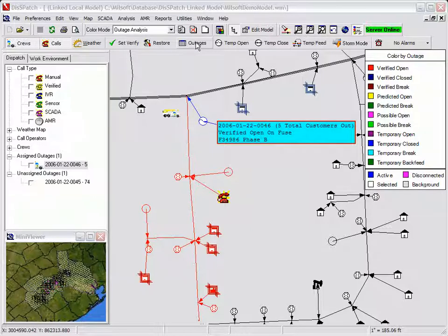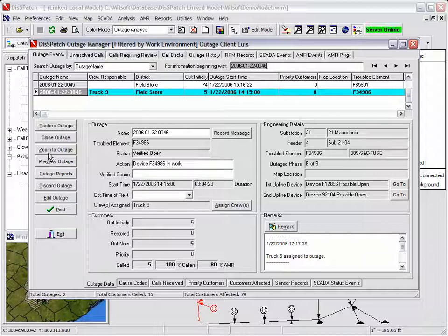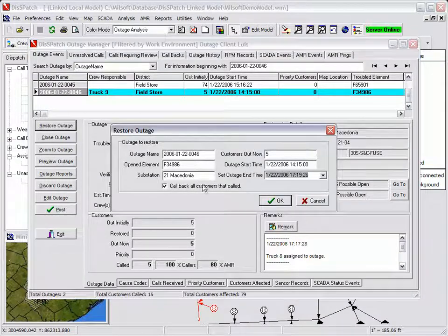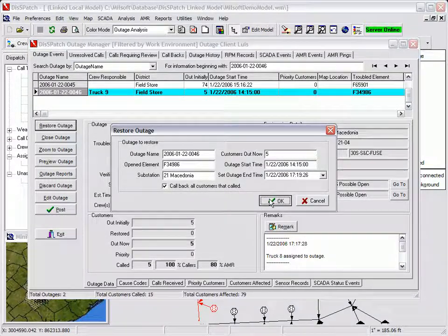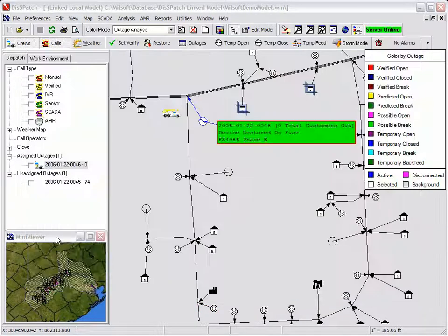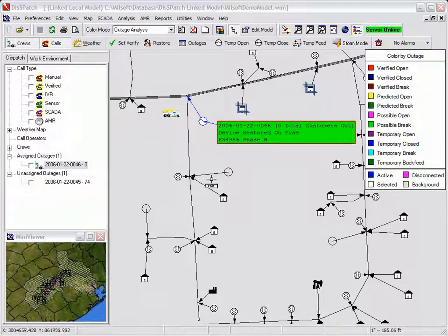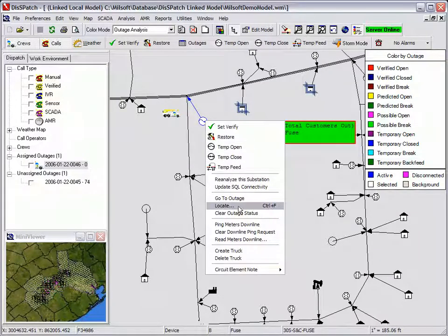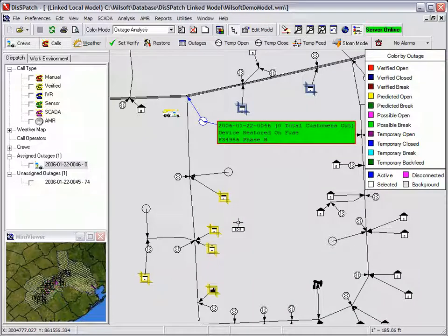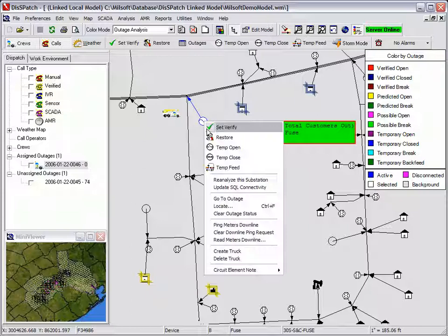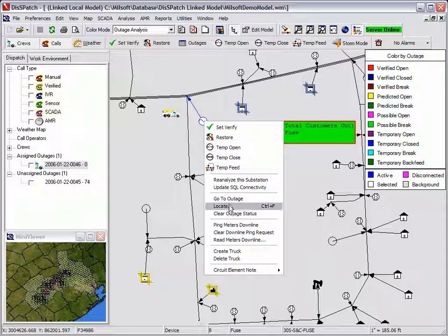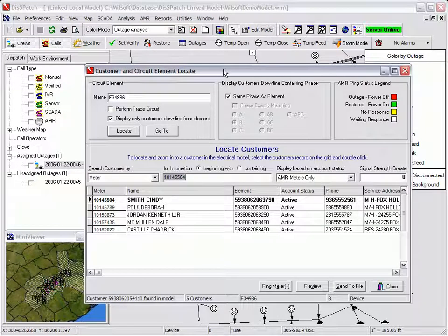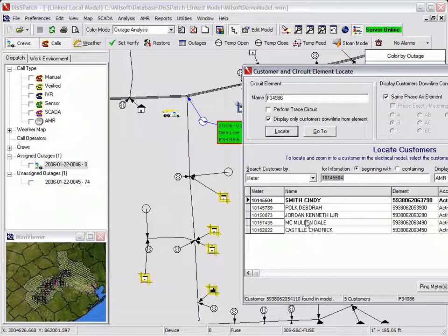The crew later calls in to report that the fuse has been repaired, so the dispatcher records the power restoration by pressing the restore outage button on the outage manager. The outage tag turns green indicating power restoration. The dispatcher then confirms power restoration by selecting ping meters downline from the restored fuse. This is done before the crew leaves the area of the outage in order to ensure that power is restored to every meter.